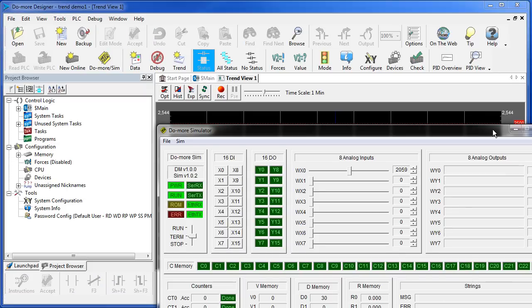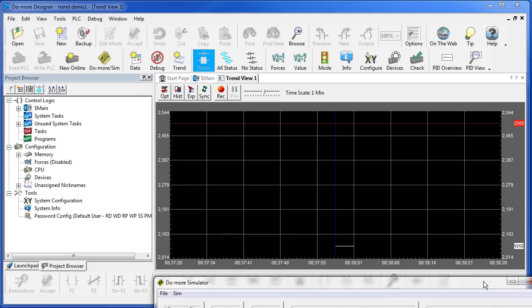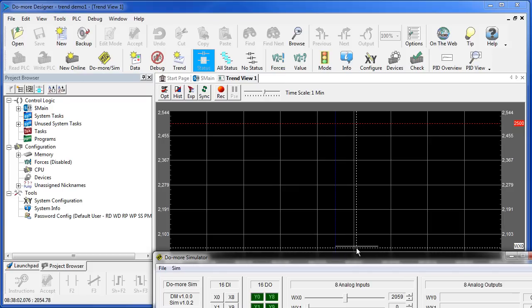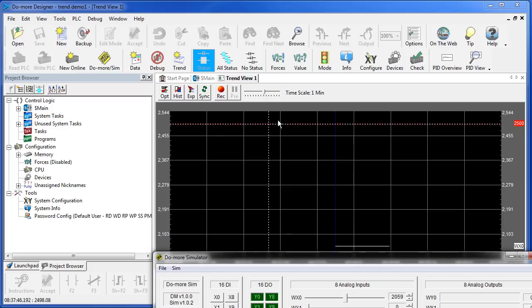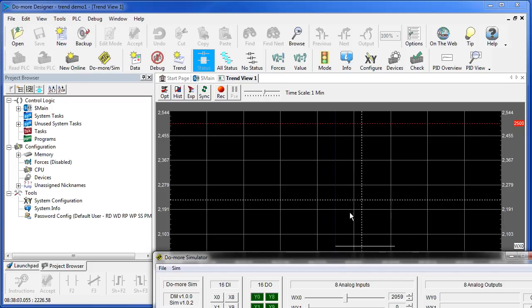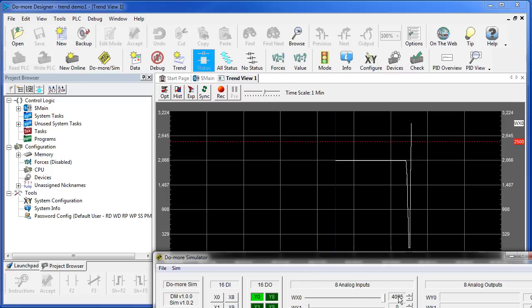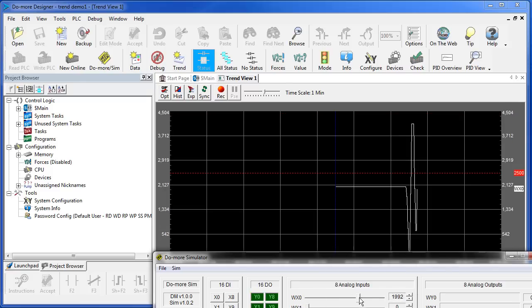I'm going to move my simulator out of the way here so we can see what's going on. The white trace is the analog value, the red trace is that 2500 constant, and if I just change my analog value you can see it bounce all over the screen and as it crosses the threshold, Y0 is turning on and off.